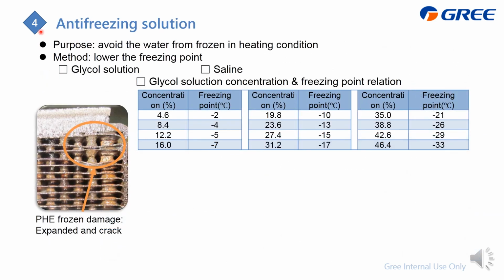Next is anti-freezing solution. The purpose of it is to avoid the water from freezing in heating mode. As you know, for the heating mode, we just cool down the water, right? And the water is very easy to freeze, especially inside the plate heat exchanger, which is the coldest. And also, here is an example. The water will expand and become ice, and make it crack, which makes the system damaged. And if the water enters the refrigerant system, it will be a disaster.